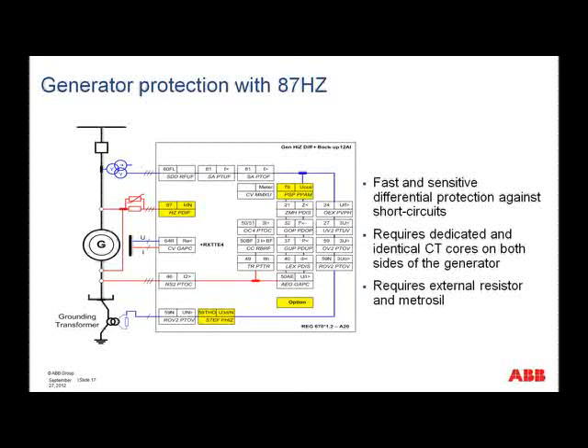Now here we see really the same as what we saw on the previous slide, but now instead of having the 87G, the low impedance generator protection, we show the application using high impedance protection for the generator, and you can see it over here. So this, of course, requires dedicated and identical CT cores on both sides of the generator, and of course then you would design the high impedance circuit, and you would have to include also the external resistor and Metrosil.